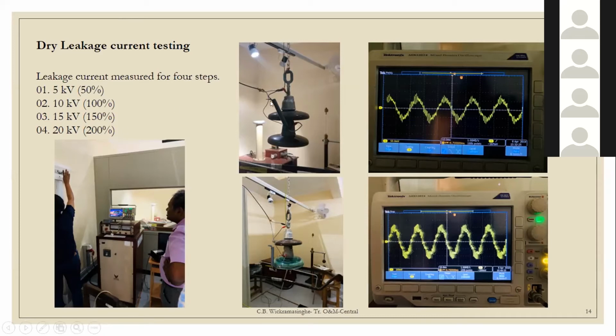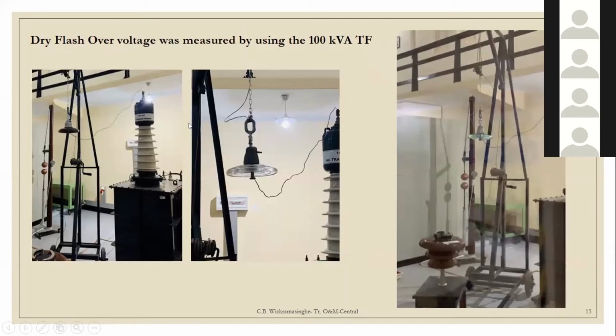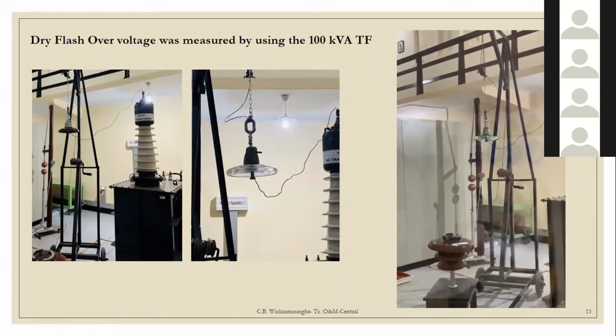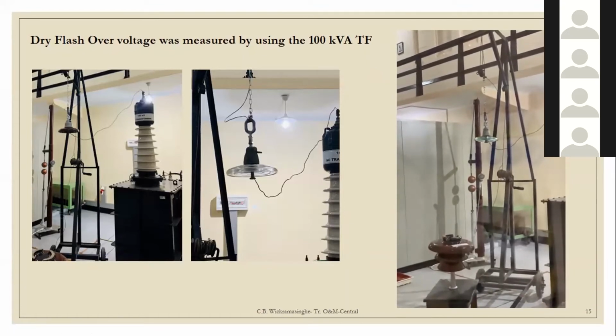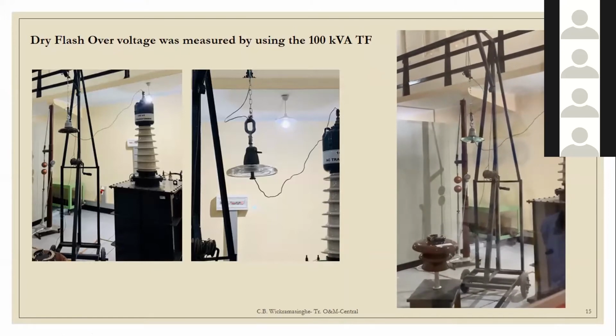Then I connected a 1 kilo ohm resistance, and by using these 2 probes, it was connected to the oscilloscope. And then I got the voltage graph here. By using this voltage graph, V equals IR, I was able to calculate the leakage current. So from that, I calculated all the leakage currents in these 4 steps. Then I measured the flashover voltage at dry condition. That was flashing over of an insulator.